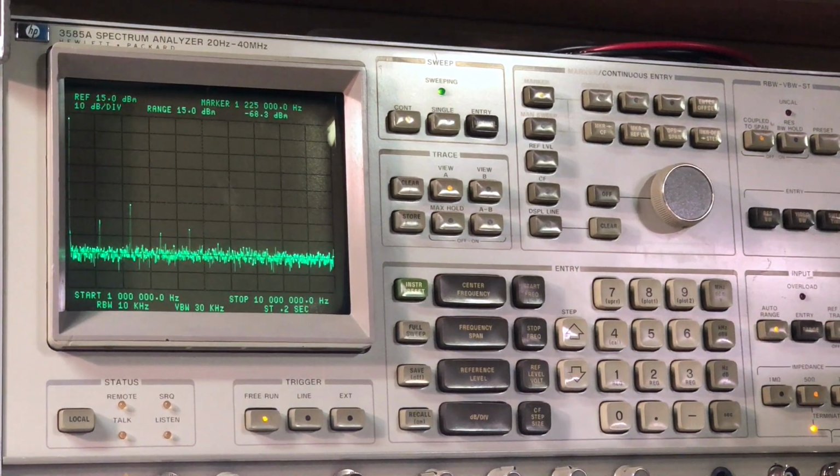Okay, I now have the DS340 synthesized function generator connected to my Hewlett-Packard 3585A spectrum analyzer. The DS340 is set to 1 megahertz sine wave output. So the spectrum analyzer is sweeping from 1 megahertz to 10 megahertz. So that will allow us to see up to 10 harmonics if they're present. And as you can see on the spectrum analyzer's display, it does show a couple harmonics showing up. Several of them are there, and then by the time it gets closer to the 10th harmonic, they're basically buried down into the noise. They're very, very low values.